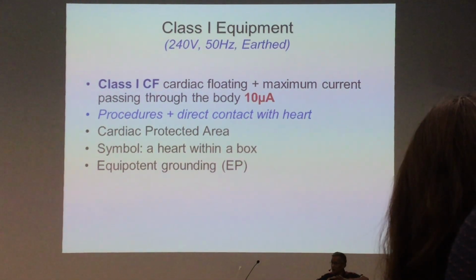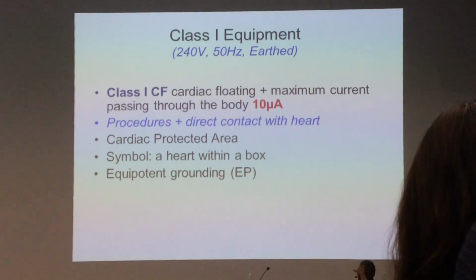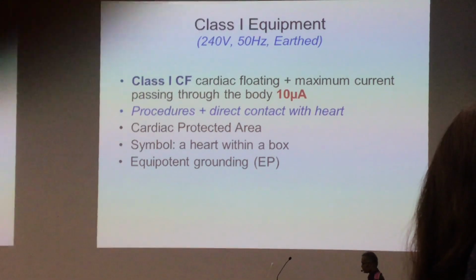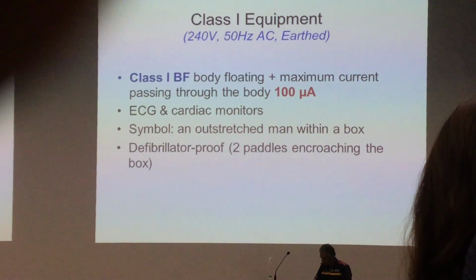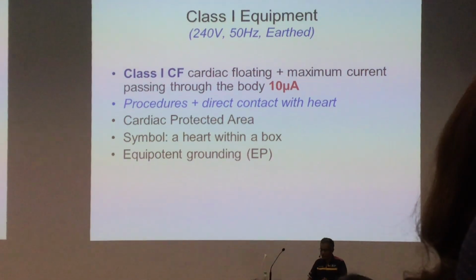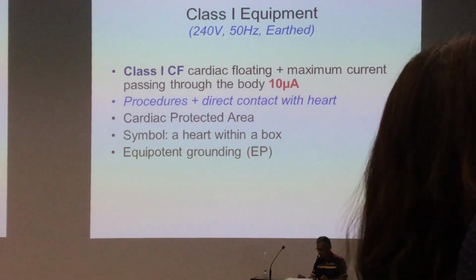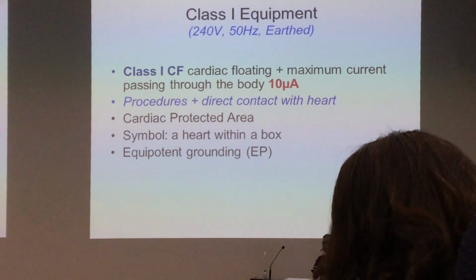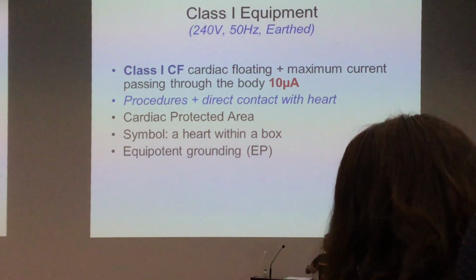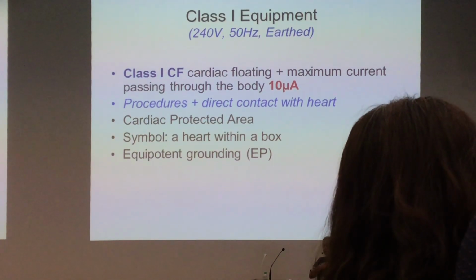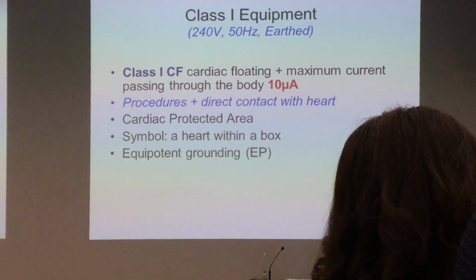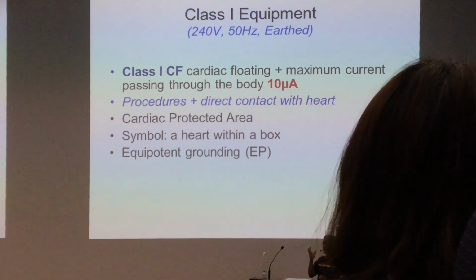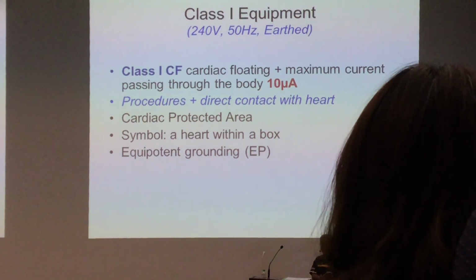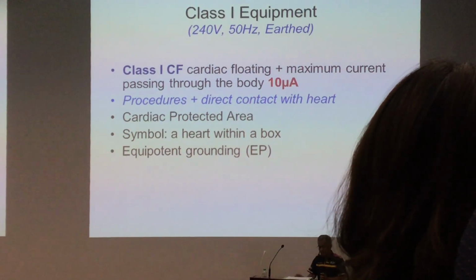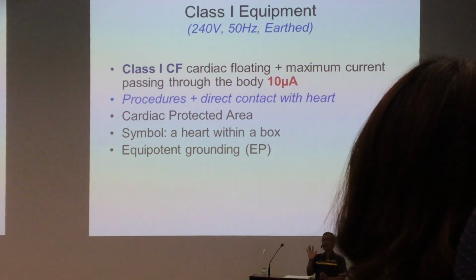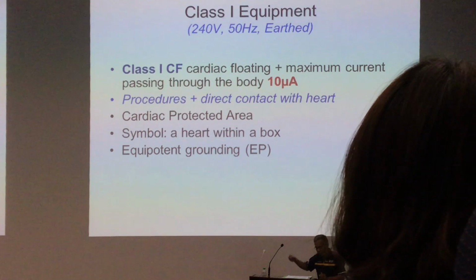Now, in the OT, you classify equipment into three, basically. The class 1. Class 1 is divided into two. Class 1 CF, where the amount of current allowed to go through the body is very minimum, 10 microamp. This is the area where you are doing intracardiac procedure. For example, inserting CVP line, pacemaker, cardiac catheterization, or CABG, any procedure where you are in direct contact with the heart. So this procedure must be done in OT with class 1 CF, where the maximum current that can pass through the body is 10 microamp.